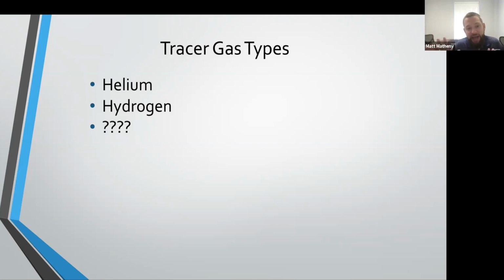So it's sort of like back to the accumulation. Hydrogen fills a nice niche market in the middle range of leak rates, where you may have a test where pressure decay or mass flow is not sensitive enough, but you don't want to go all the way to helium, which is a little more expensive than diluted hydrogen. So it's a nice fit for certain applications.